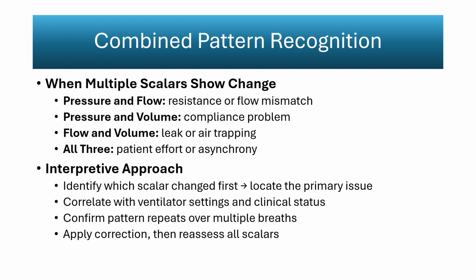An abrupt volume drop mid-inspiration indicates premature cycling or active exhalation during the inspiratory phase. If the ventilator ends inspiration too early, or if the infant forcefully exhales against incoming flow, the inspiratory volume falls suddenly. This is a hallmark of asynchrony. Adjusting the cycling criteria so inspiration ends when the infant naturally transitions to exhalation restores a smooth, complete inspiratory waveform. These volume patterns provide critical insight into leak magnitude, timing mismatch, and adequacy of exhalation, allowing tailored adjustments that improve synchrony and support effective ventilation.